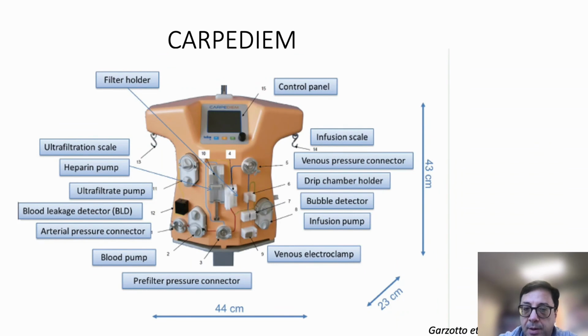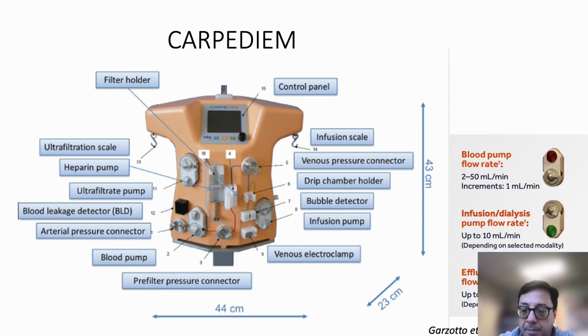The really interesting part about this machine is that it's got lots of bells and whistles that are designed from the ground up to be for neonates. The accuracies are very accurate. The ability to calibrate and choose different blood flows is excellent. And the blood pumps have a very unique property in that they have a 3-pronged approach, giving less swing on your peaks and troughs of your pressures, thus allowing a higher blood flow for a given access size.